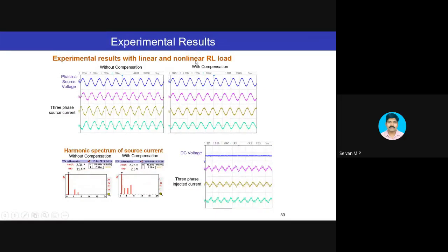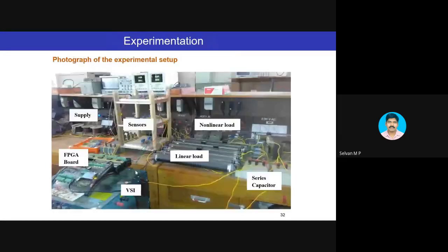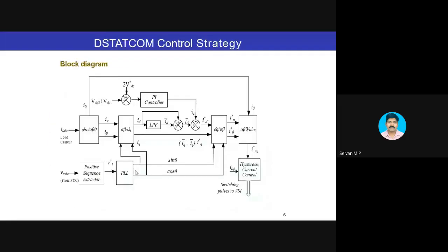This is for linear and nonlinear load. So I have a voltage and look at the current before connecting the STATCOM. Then after connecting the STATCOM, it becomes sinusoidal as well as in phase with the voltage. So the power factor is improving. THD is also getting reduced from 11 to 2.6. So linear and nonlinear load, where you need reactive power supply as well as the harmonic current, can be mitigated with the help of the STATCOM. The control required is the same, whether you need reactive power compensation or a harmonic compensation, the loop involved is only this.